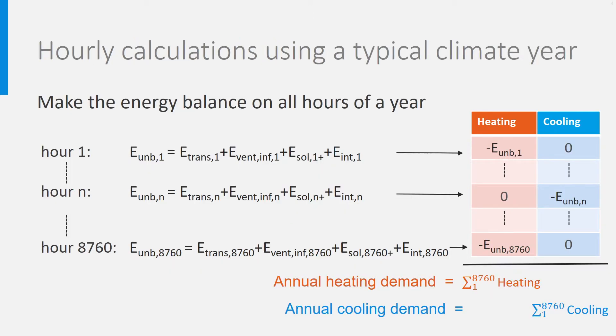If we have hourly temperature and solar radiation data, for instance from a meteorological institute, we can make very easily an energy balance per hour. And if we can make it for one hour, we can also make it for more hours and for one complete year. There are 8760 hours in one year. Happily, we don't need to do this manually — we can use software like Excel or Python or similar. This is also the principle used by most building simulation software like EnergyPlus, ESP-r, TRNSYS, etc.